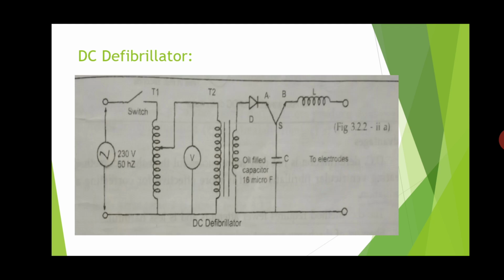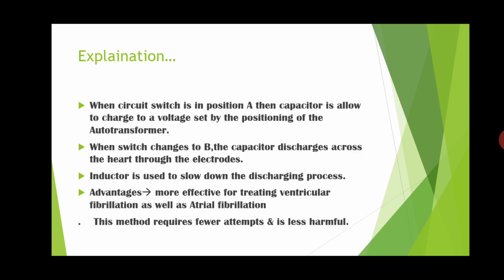Then we'll see the advantages of the DC defibrillator. The first advantage is the DC defibrillator is more effective for treating ventricular fibrillation as well as for correcting atrial fibrillation. The second advantage: the DC method requires fewer attempts and is less harmful.